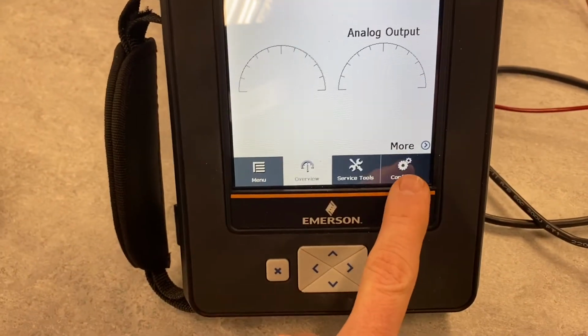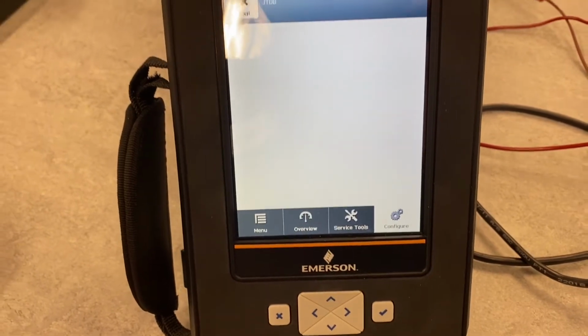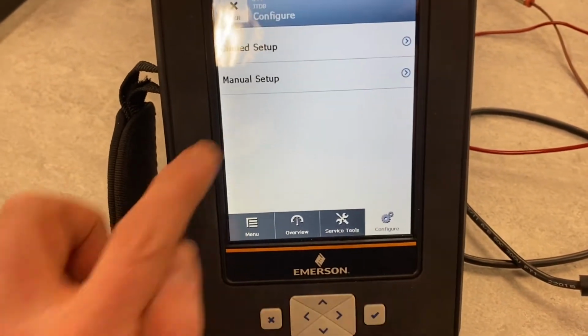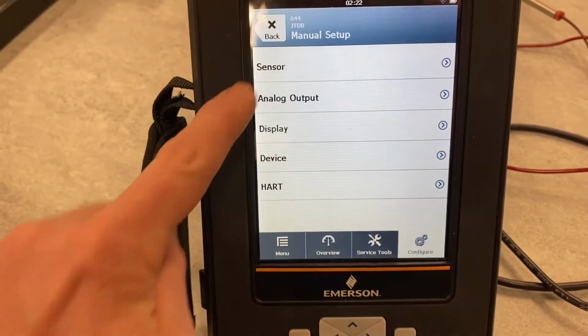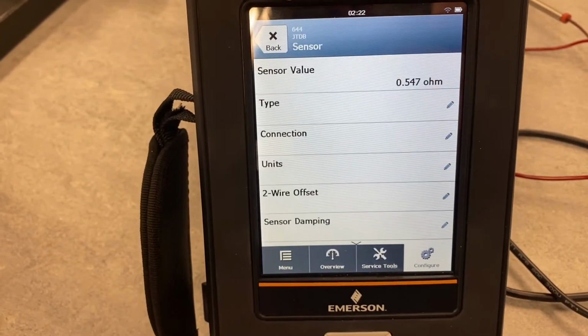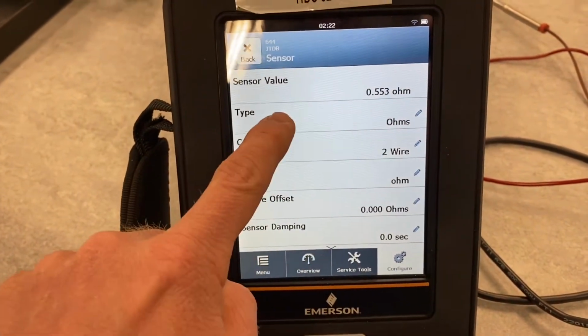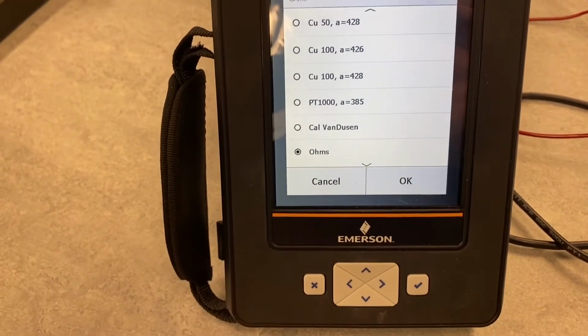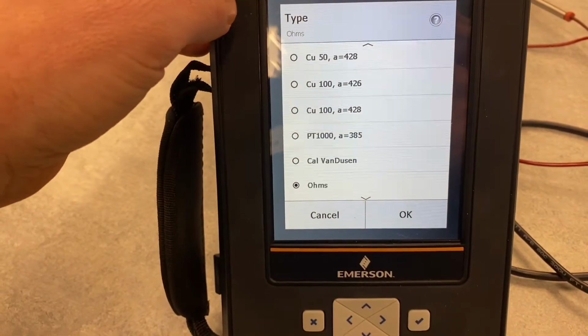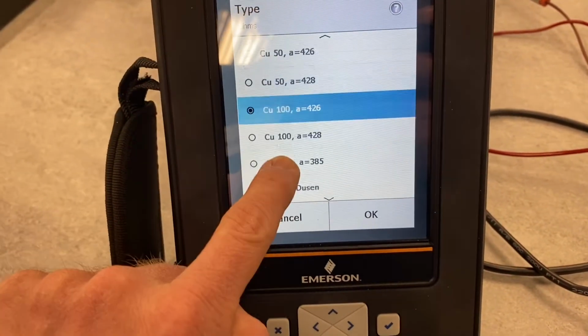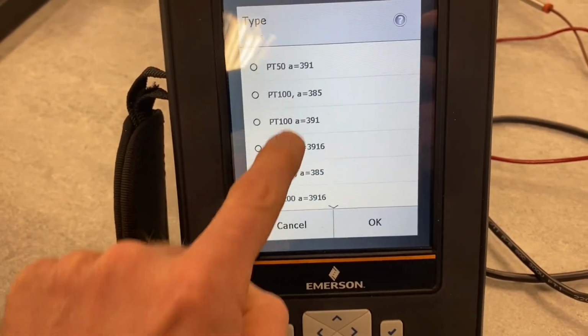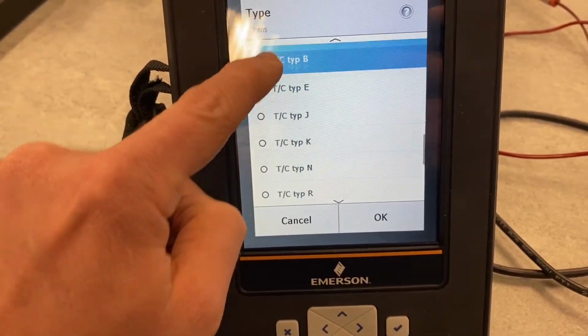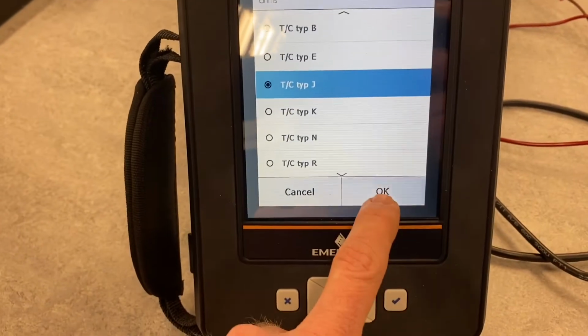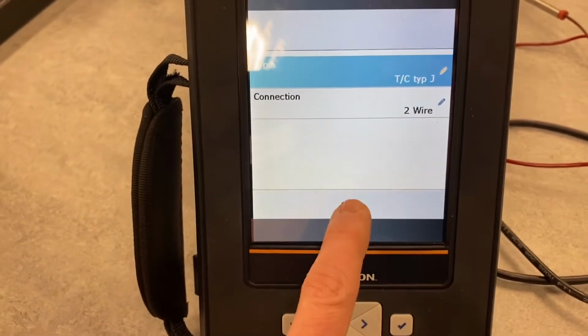What we're going to want to do is configure the device. So we're going to click on the configure button down here, and then go to manual setup, and we want to change the sensor right here. So we'll click on the sensor, and right now it's an ohm type. We want to change it to a thermocouple, so we should be able to edit this. And we want to find a type J thermocouple here. Let's see if it has our type J in here. Down here, type J, so we select type J, click OK. It's 2-wire, so click OK.